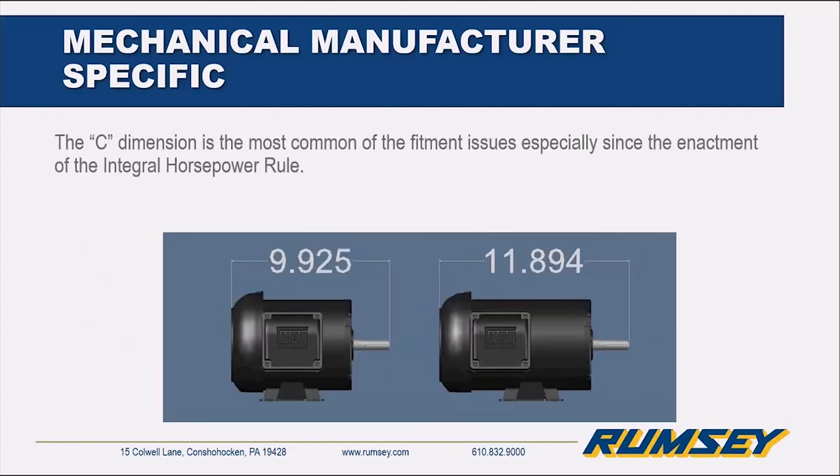On the C dimension: this is the same size motor from the same manufacturer, but they have different tolerances showing the minimum and maximum C dimension within that frame size. You may not think two inches is a lot, but when you get to something where the motor is kind of shoehorned into a machine application, you may not be able to get that 10-inch motor in where you now have an almost 12-inch motor. It's just not going to fit.